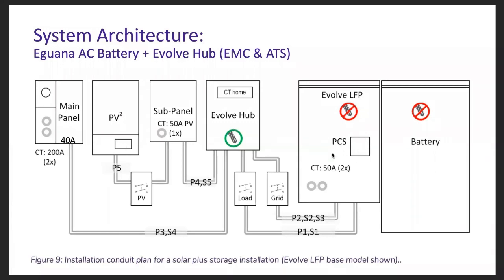And then by routing another grid tied inverter, the battery system itself, through the hub, what we're doing is regulating through this certified interconnection device the discharge of that battery based on the real-time PV production, so that the combination of the PV inverter plus the battery inverter never exceeds the backfeed rating of that breaker. So you can, in effect, close to double the time of the day that you have available generator, renewable energy generation sources. More details on that you can see in the Evolve Hub manual, but I think it's probably one of the most important features of the Evolve Hub setup: the ability to bypass the extra cost to your customers and time of installation, and ease of design using the Evolve Hub setup.